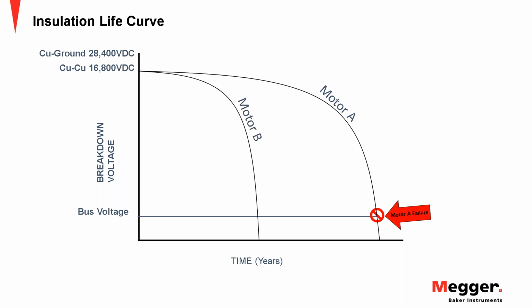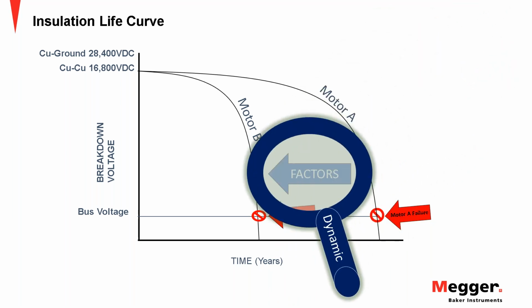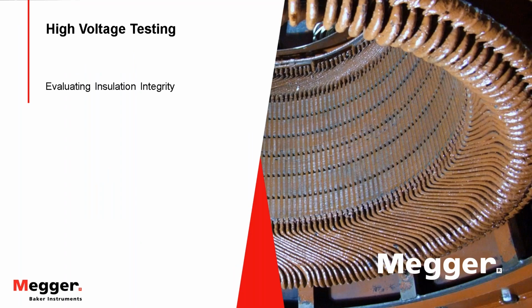Now there might be another motor of the same design that fails in half the time, and the reason is probably because it has to endure a harsher environment. There's more heat present, or the stresses are different. Maybe the starting interval is more frequent. Lots of different factors there. And to help us understand the differences between the operational conditions of motor A and motor B, that's again where dynamic testing comes in to reveal those factors that can push us towards a shorter life, a less reliable operating environment. So that's how dynamic testing fits into the mix.